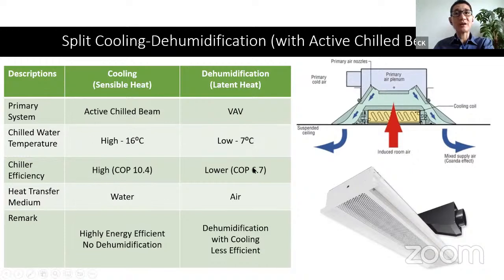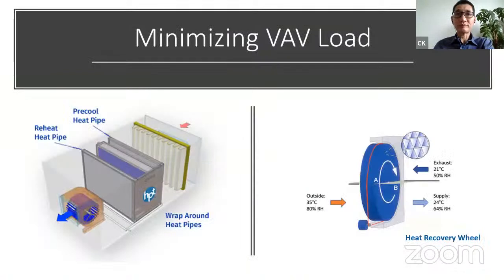Although we use a conventional chiller with a COP of 6.7, we can target to minimize the cooling done by the VAV system, and I'll show you how we do that. To reduce the cooling by the VAV system, so that most of the cooling is done by the chilled beams, because the chilled beam is more efficient.